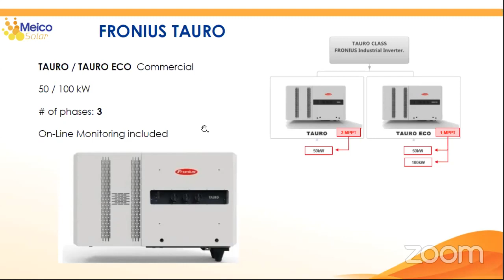Something really interesting about this inverter, that we haven't seen before with Fronius or SMA, is that you can wire the inverters with daisy chaining in the AC wiring. This is great because you don't have to run separate cables from inverter 1, inverter 2, up to inverter N, each to the AC connection panel. Instead, you can daisy chain the AC wiring from inverter 1 to 2, to 3, up to inverter N, and then connect that to the AC panel.